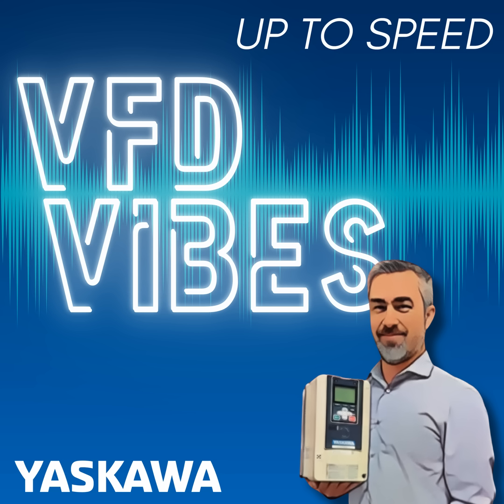So in the case of a line reactor, this is a component you put on the input of a drive, and it helps filter out these higher frequency harmonics. There's another component that's similar to a line reactor called a DC bus choke. That is either one or two components, depending on the design.